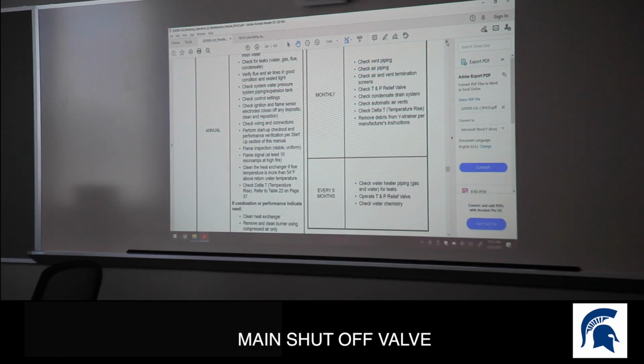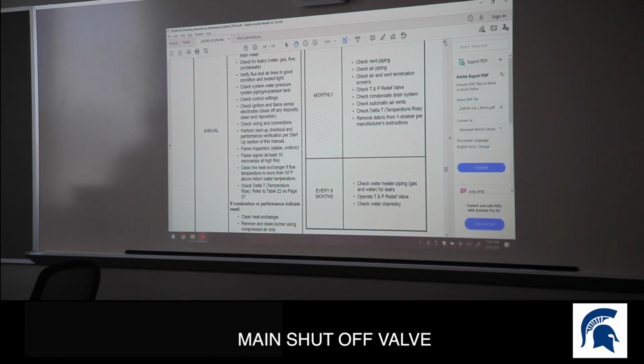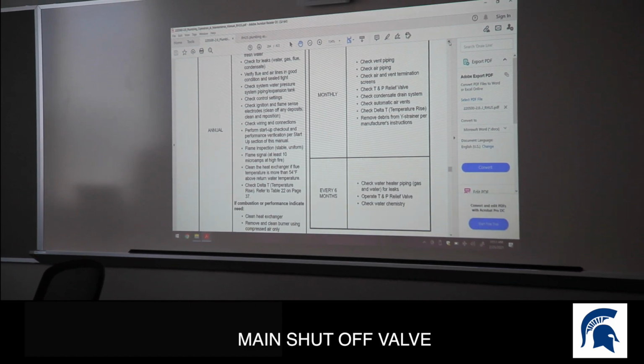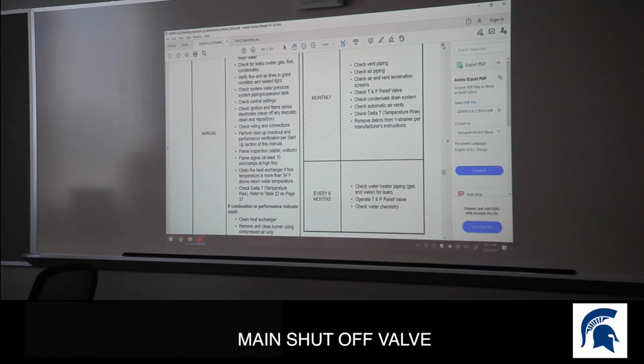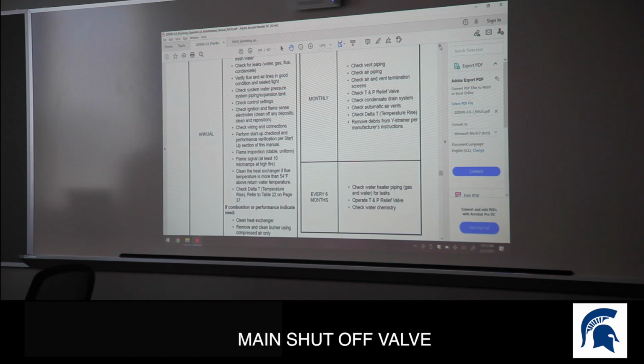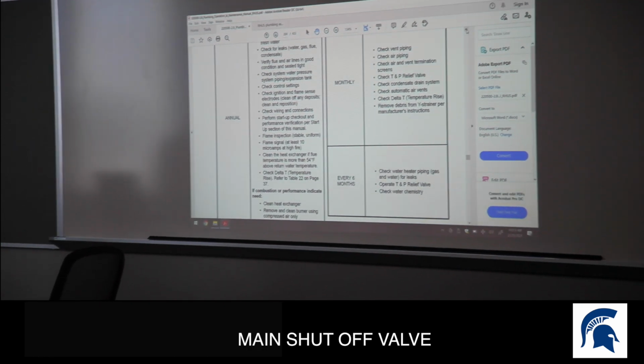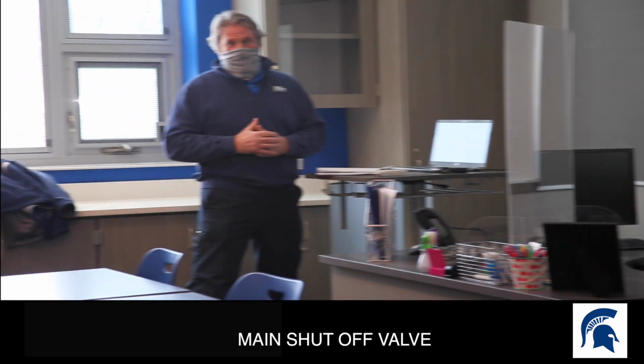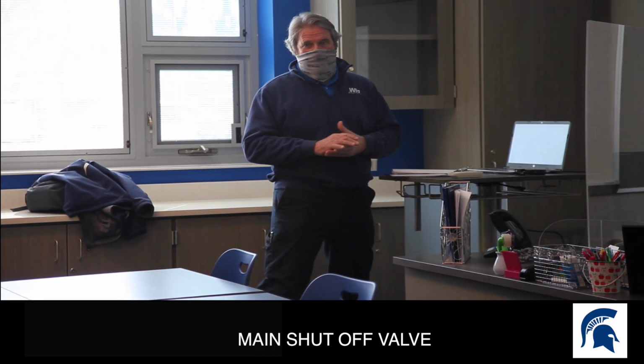13 degrees, 45%. So it has to be that. And you keep an eye on that. If you catalog that, then you'll know, hey, it's dropping here. I'm getting clogging in that heat exchanger. You would be able to flush that out if needed.